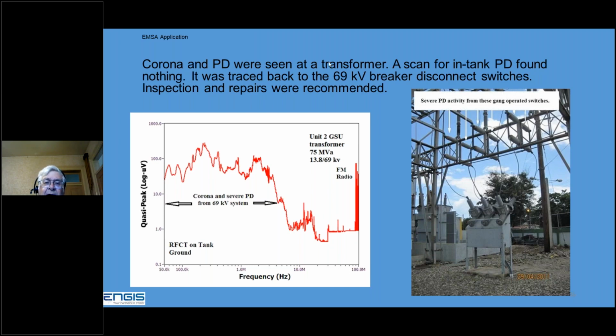So we walked the line down to the switch yard, which was almost a kilometer away. Very good distance between the transformer and the disconnect switches. And this is where all the arcing activity was going on. Gang operated disconnect switches on an SF6 breaker going to that transformer. It's near the Caribbean, a lot of salt water, a lot of rust. So they needed to clean those switches up. There was a problem with the switchgear.